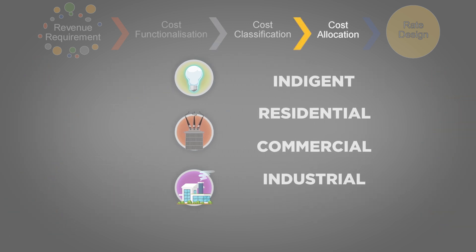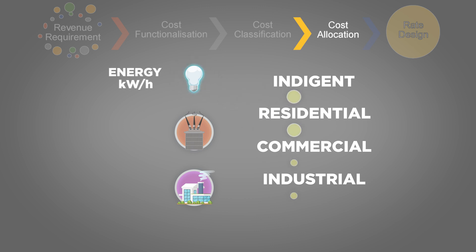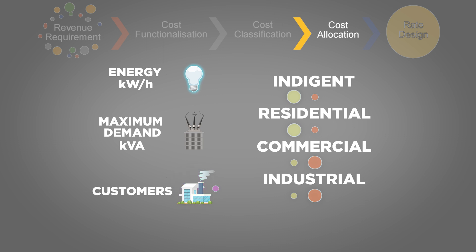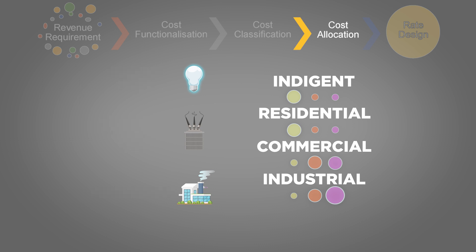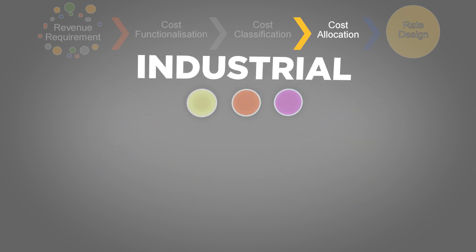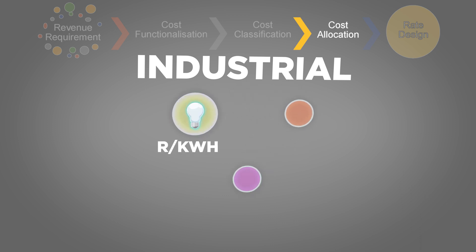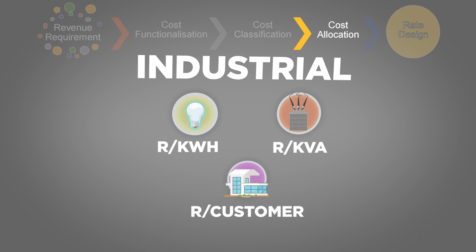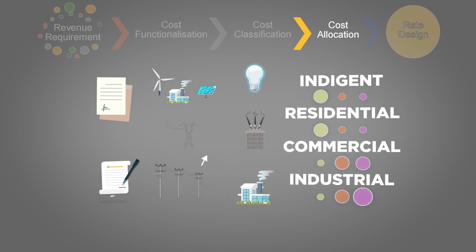In the fourth step, these cost groups are allocated to your different customers, reflecting the cost that they cause. The energy-related costs are allocated according to each group's share of total energy consumption. The demand-related costs are allocated using each group's contribution to the network's peak demand. The customer-related costs are allocated using a weighting based on how much more expensive large customers are to service relative to small customers. The cost allocation step provides you with the cost of supplying each customer group in Rand per kilowatt hour, Rand per KVA, and Rand per customer. That's the cost of supplying each customer group.